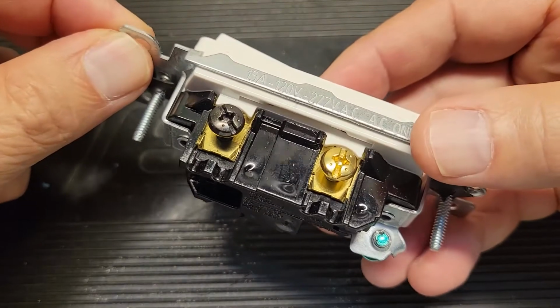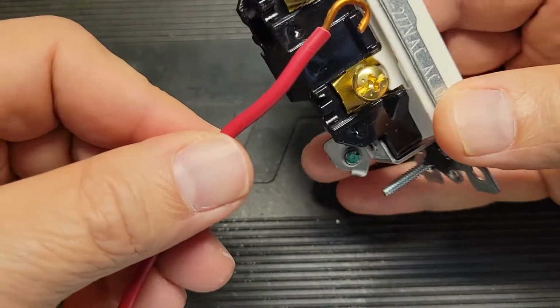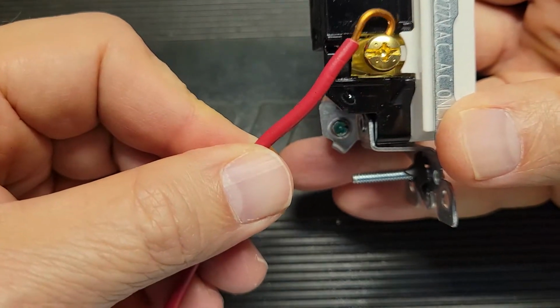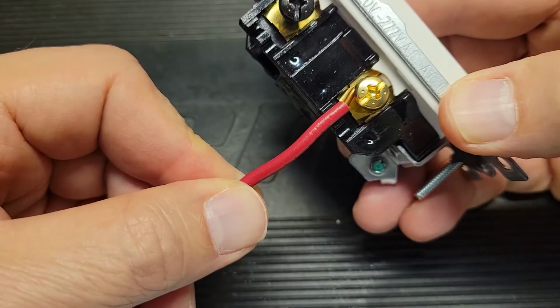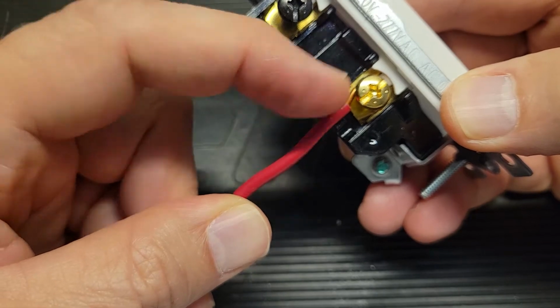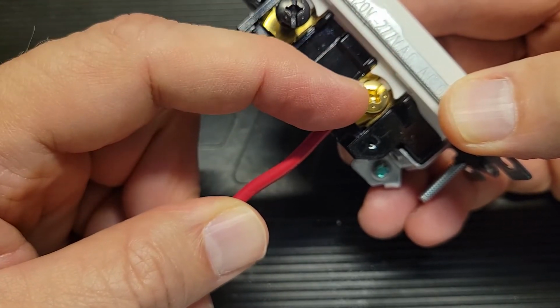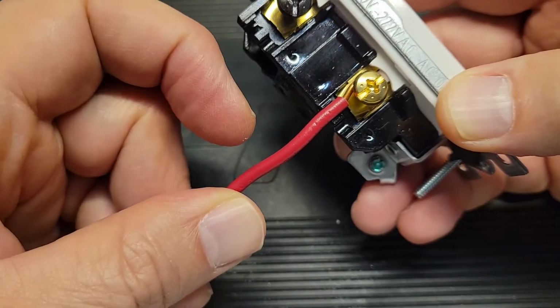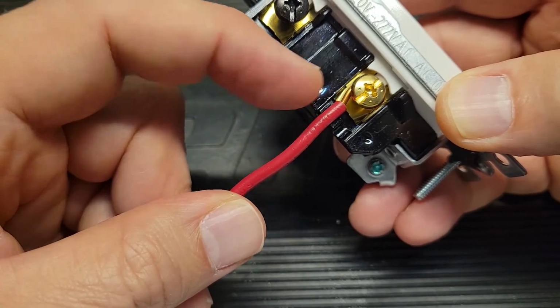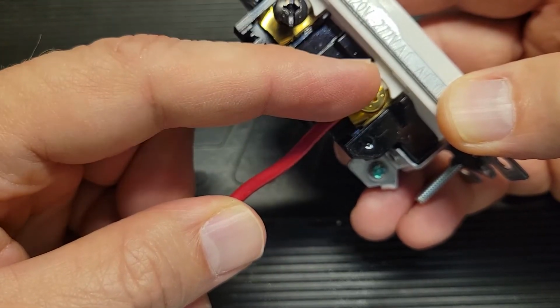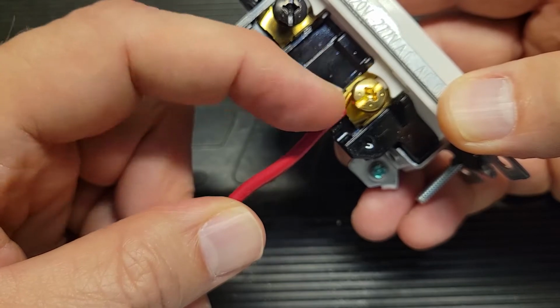With this switch, there are three different ways of connecting the wire to it. You can use the side mount method, in which you put a loop on the wire, insert it, and turn the screw clockwise to lock it down. Make sure your loop is going clockwise so that it's tightening it, not loosening it, as you turn the fastener clockwise.